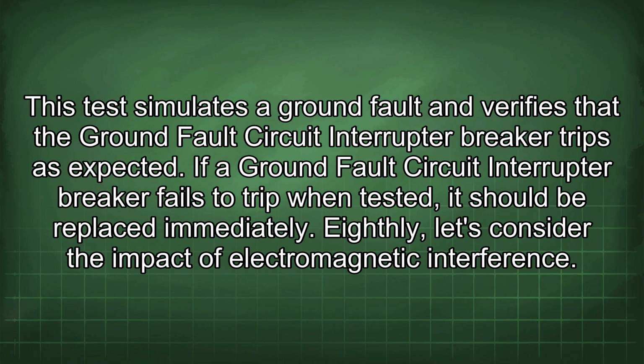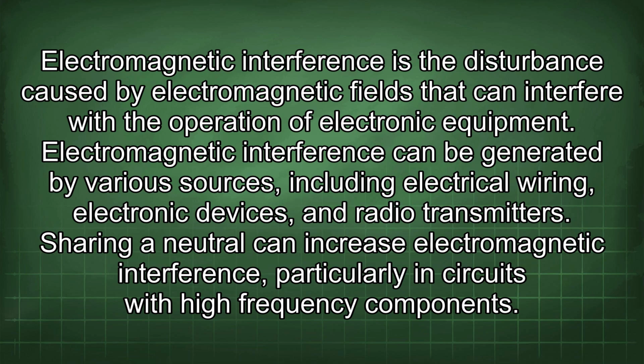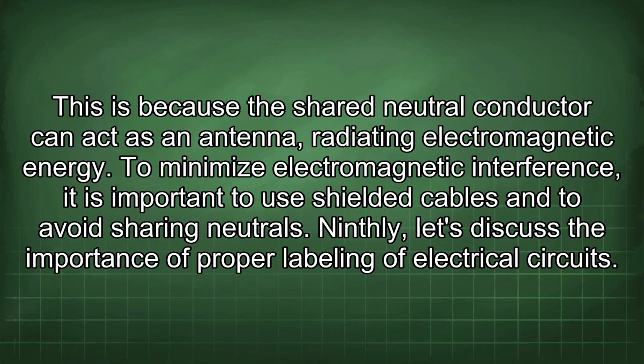Eighthly, let's consider the impact of electromagnetic interference. Electromagnetic interference is the disturbance caused by electromagnetic fields that can interfere with the operation of electronic equipment. Electromagnetic interference can be generated by various sources, including electrical wiring, electronic devices, and radio transmitters. Sharing a neutral can increase electromagnetic interference, particularly in circuits with high-frequency components. This is because the shared neutral conductor can act as an antenna, radiating electromagnetic energy. To minimize electromagnetic interference, it is important to use shielded cables and to avoid sharing neutrals.